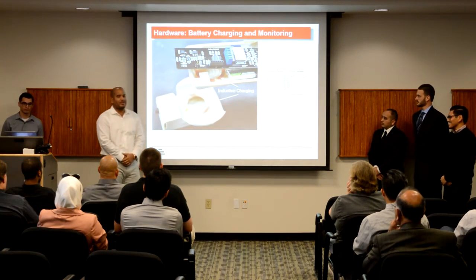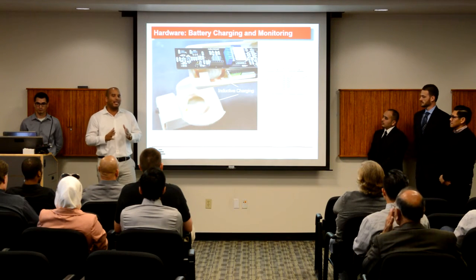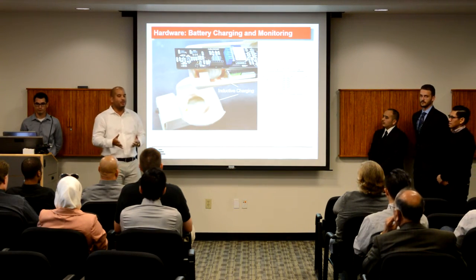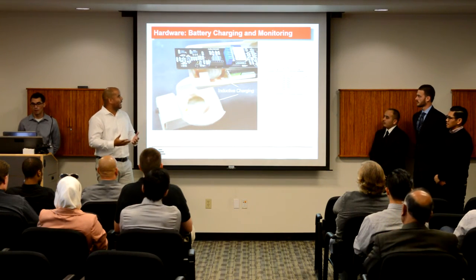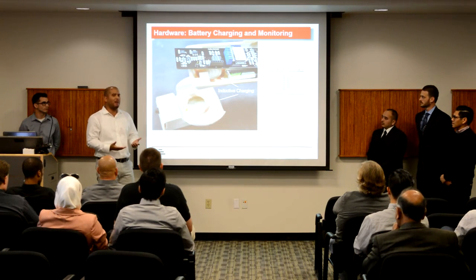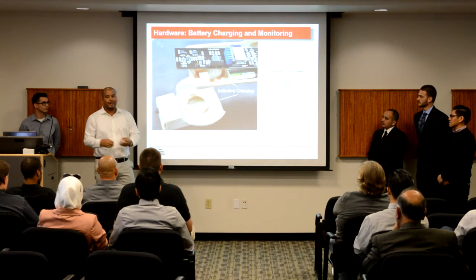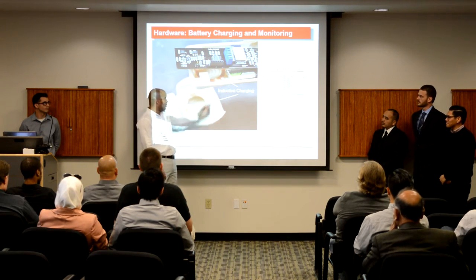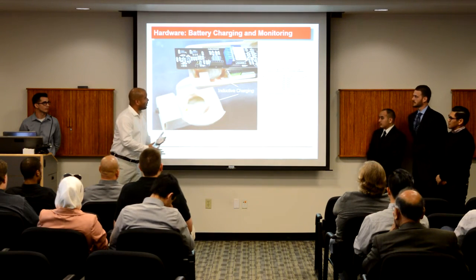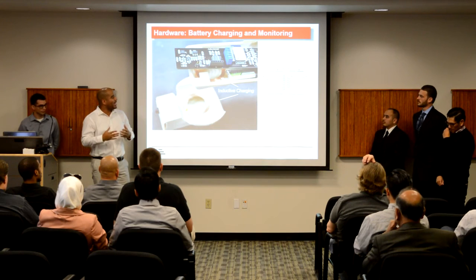Thank you, John. My name is Juan Rodriguez, and today I'll be discussing the battery charging management system. When I started designing the system, I was focused on one key parameter our sponsor stated: our device needs to be able to expand into hospitals and clinics, not only home use. Most hospitals would like a device that can be easily washed and cleaned to remove germs. This requires a hermetically sealed device, and we can't do that with conventional charging wires and cables. So we decided to go with inductive charging. You can see the coils here, along with a coulomb counter and battery management chip. With a 9-volt input, a turn ratio gives us a 5-volt output at our device, and going through the battery charge management chip, we can easily control the current.